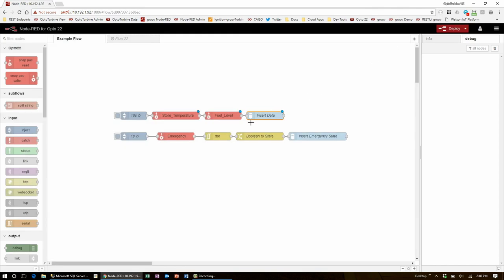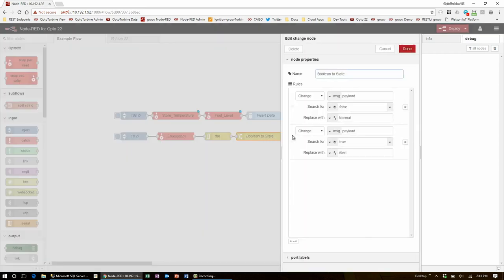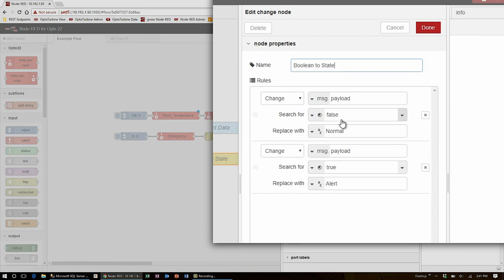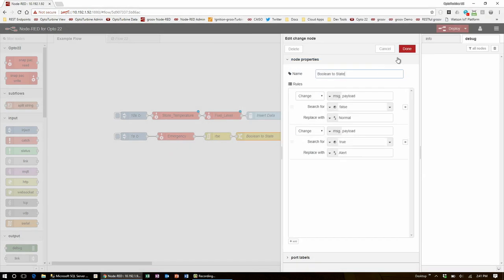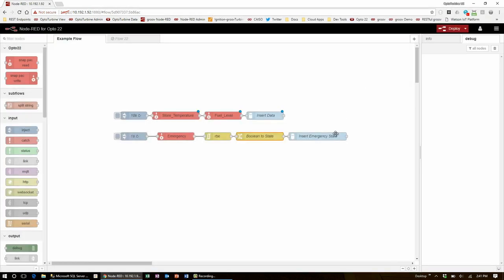State data is done a little differently to time series data. Instead of regularly reporting the value, I constantly scan the status and only let the flow continue when it changes. Once I know the emergency switch has been toggled, it goes into a change node where I turn the true false value of the switch and replace it with a string for a normal or alert status, and then that is inserted into the table. To get another piece of data, I'll need another snap pack read node.